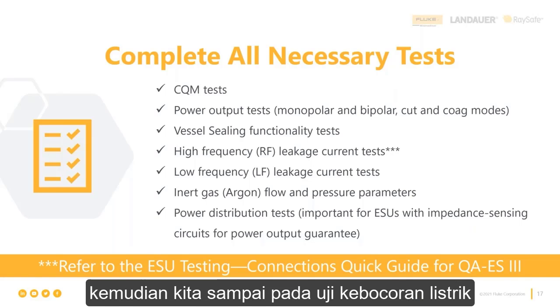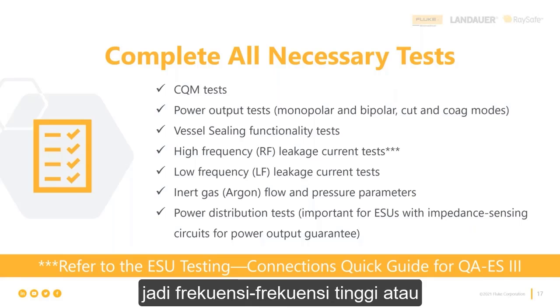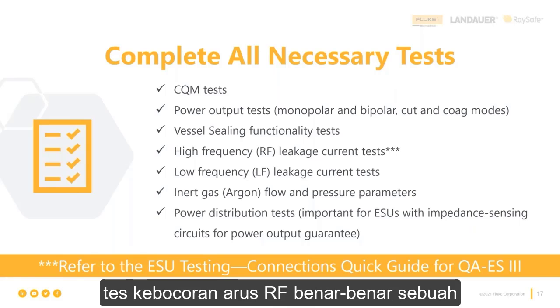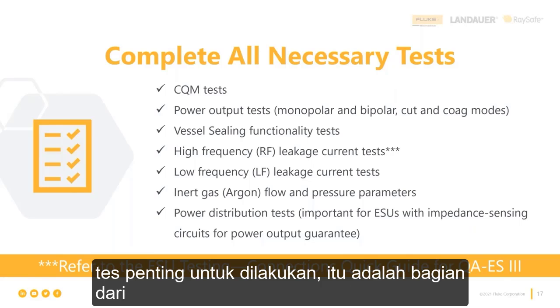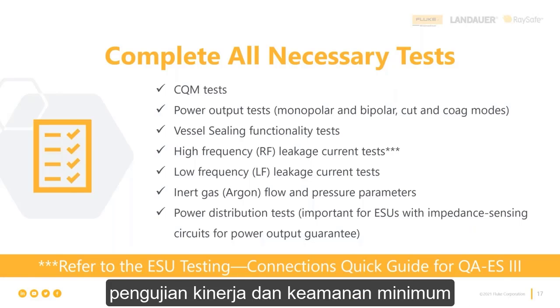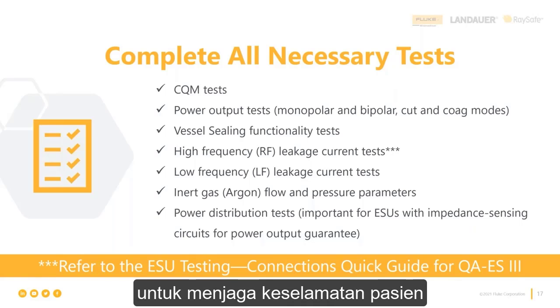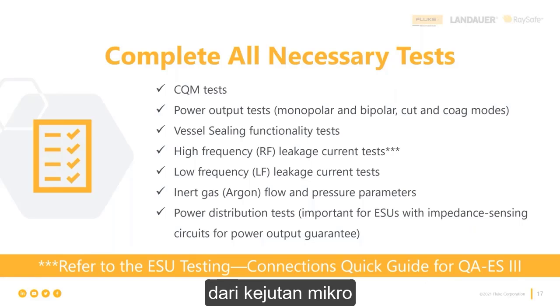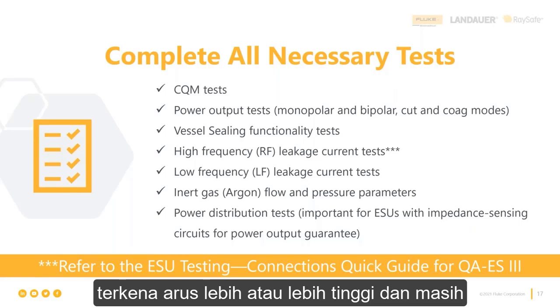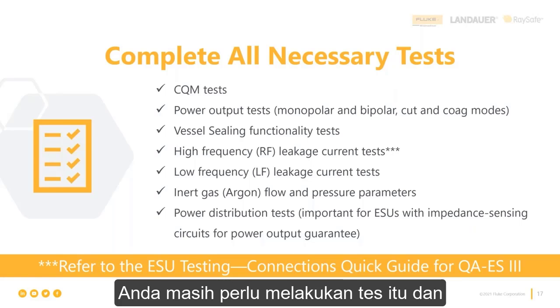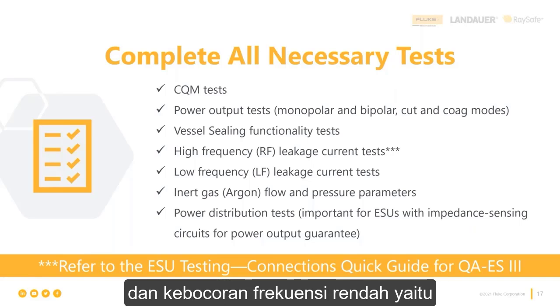Then we get to the electrical leakage test. So the high frequency or RF leakage current test is really an important test to do. It is part of the minimum performance and safety testing to keep the patient safe from microshock. Even at RF, which the human body can take more or higher current from and still be okay, you still need to do those tests and know how. And the low frequency leakage, which is our regular electrical safety tests, also needs to be done, and all of those have to pass.